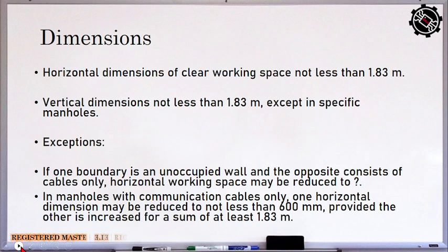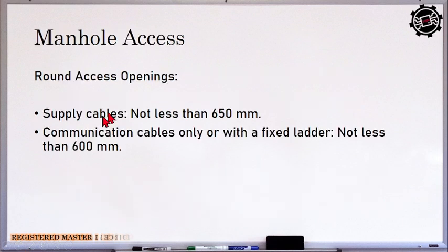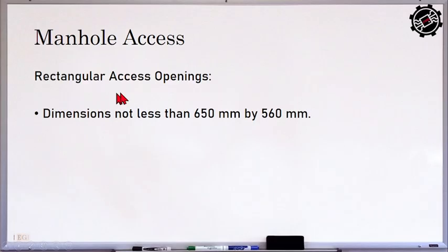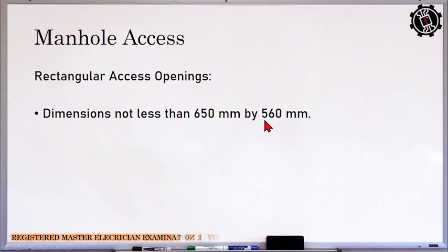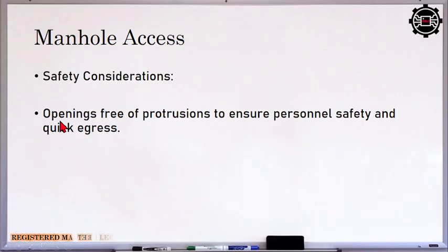Okay, so manhole access, so supply cable. So the access to supply cable sa ating manhole, so not less than 650 mm. For communication cable or with fixed ladder, so not less than 600 mm. Okay, so if our manhole is rectangular access, so the dimension must be 650 mm by 560 mm. So ito yung kanyang dimension, 650 mm by 560 mm. So safety considerations for manhole access: openings free of protrusions to ensure personal safety and quick egress. So yung kanyang mismong opening, walang mga sharp objects na pwedeng maaksidente yung ating mga qualified personnel na papasok sa ating manhole.